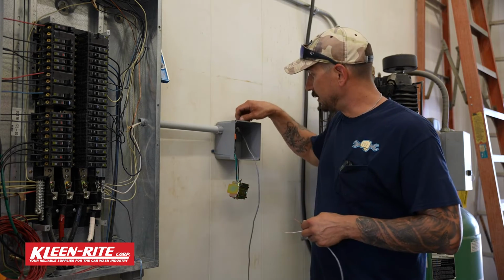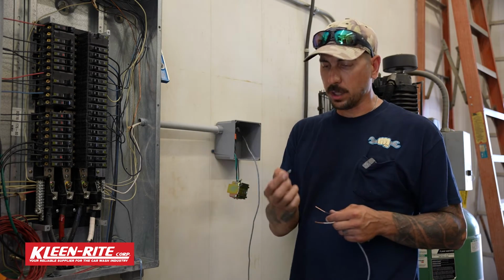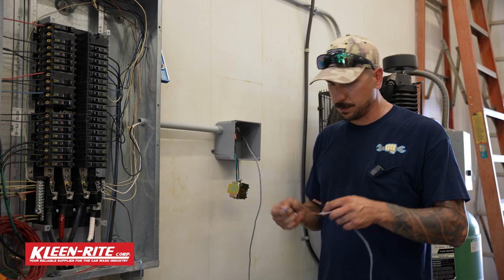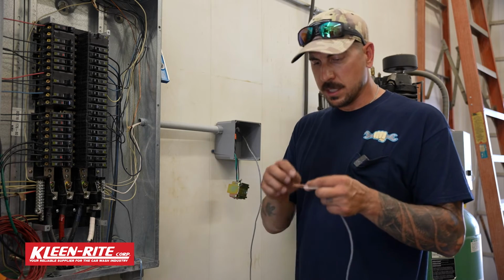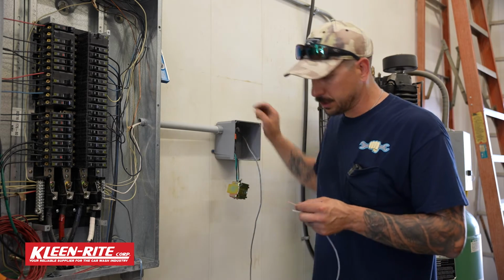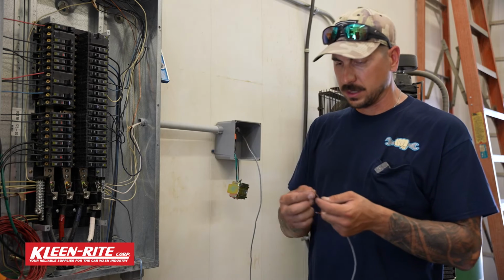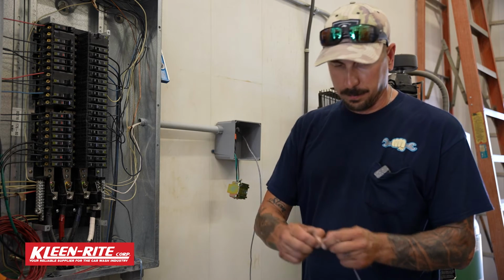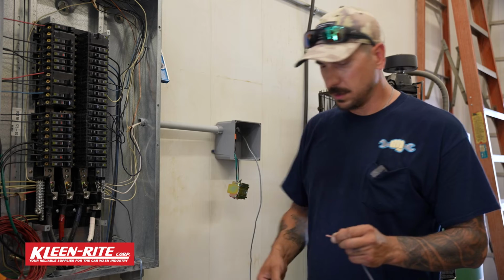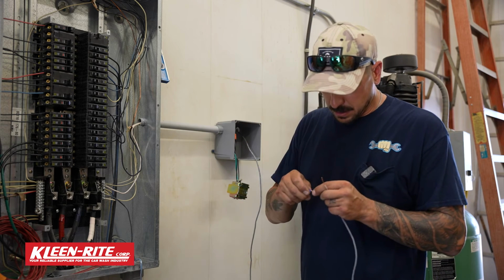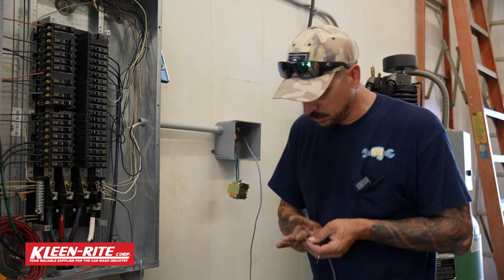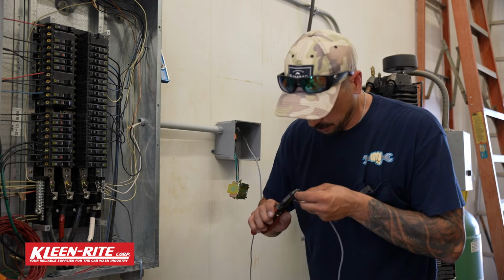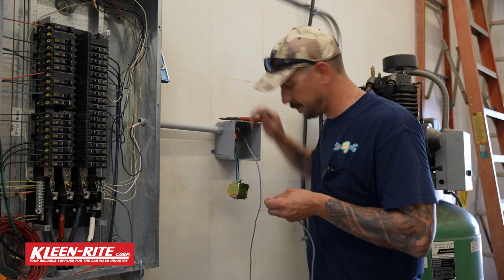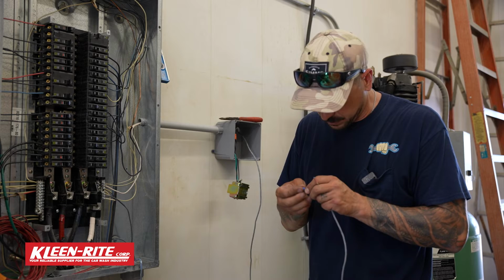So a trick is if you have to use a fork terminal big enough to fit on a post, but your wire's a little too small to fill that up and get a good crimp on it, you can strip it twice as long, bend it over on itself, twist it down, and then get it into that fork terminal to fill that space up so you know it won't slide loose.